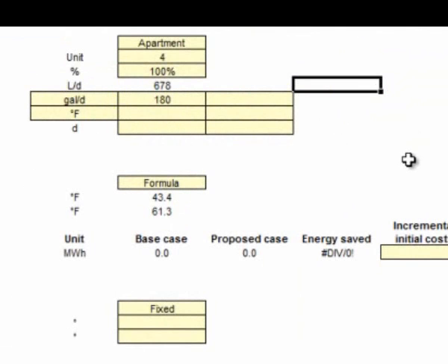Now, there's some factors involved here. So in essence, when we talk solar thermal systems, the gallons per day for total occupancy usage in this case is about, typically we say about 20 gallons of hot water per person per day. So in this case, and I'm not exactly sure how the equations of RETScreen are when it comes to apartments as opposed to the residential section, but we're giving ourselves about 180 gallons of storage on site to hold that. And so let's just keep that if we build a new system, a solar thermal, let's keep it at 180.